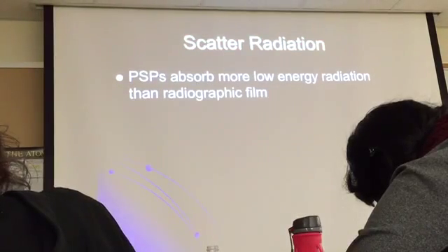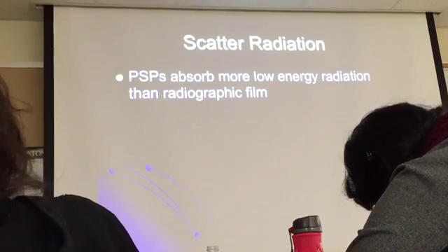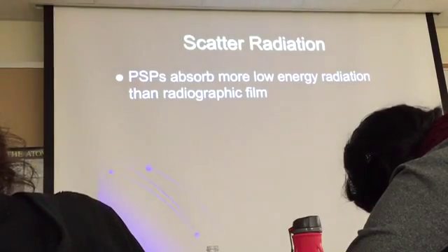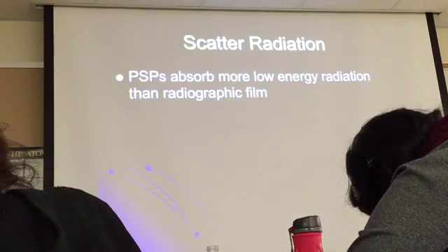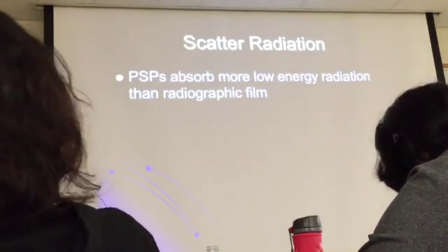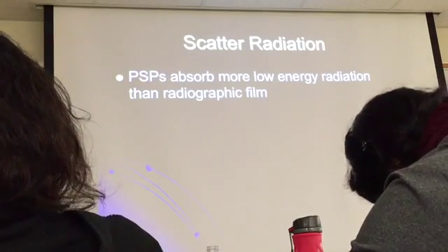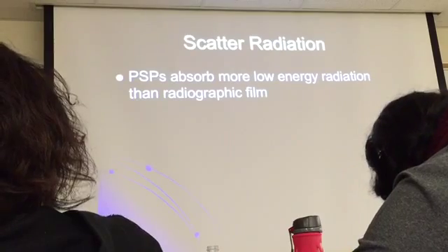All right, so scatter radiation. PSP absorbs more low energy radiation than radiographic film. And so you have to be very careful with CR plates and DR systems. You have to collimate very tightly. That's one thing.